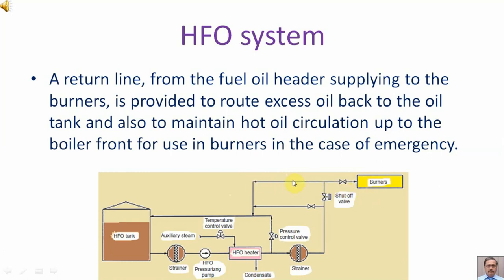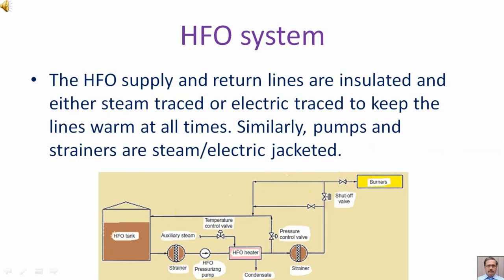The HFO return line is provided to route excess oil back to the oil tank and also to maintain hot oil circulation up to the boiler front for use in burners in case of emergency. The HFO supply and return lines are insulated and fitted with either steam tracing or electric tracing to keep the lines warm at all times. Similarly, pumps and strainers are steam or electric jacketed.